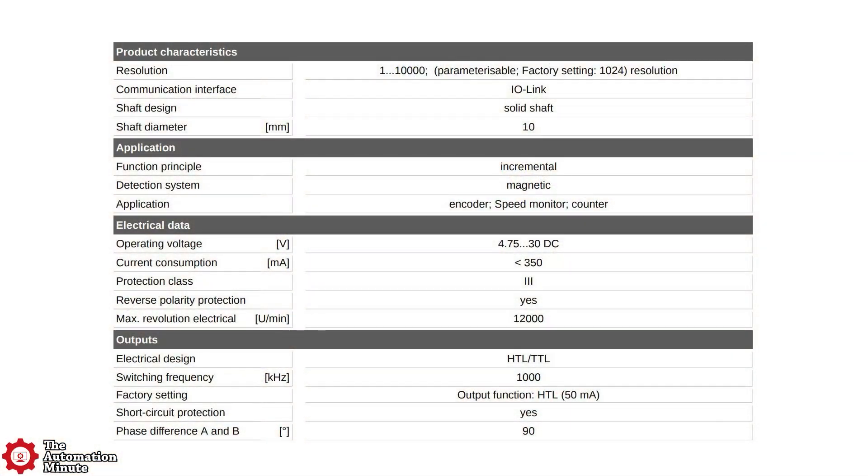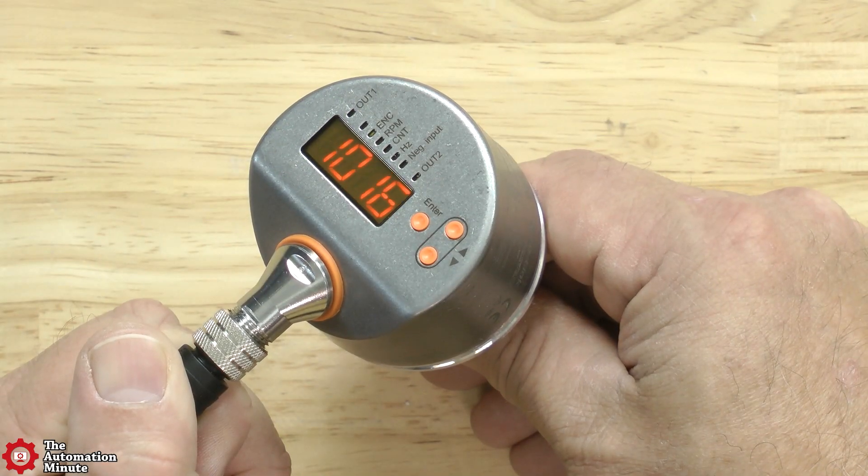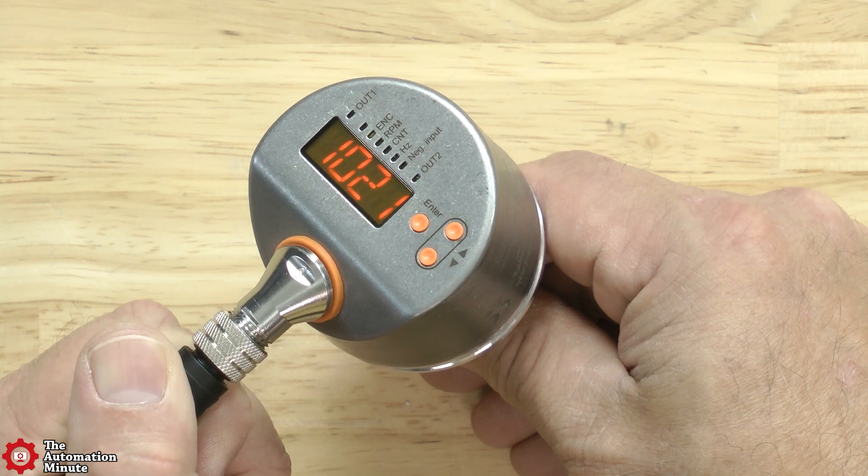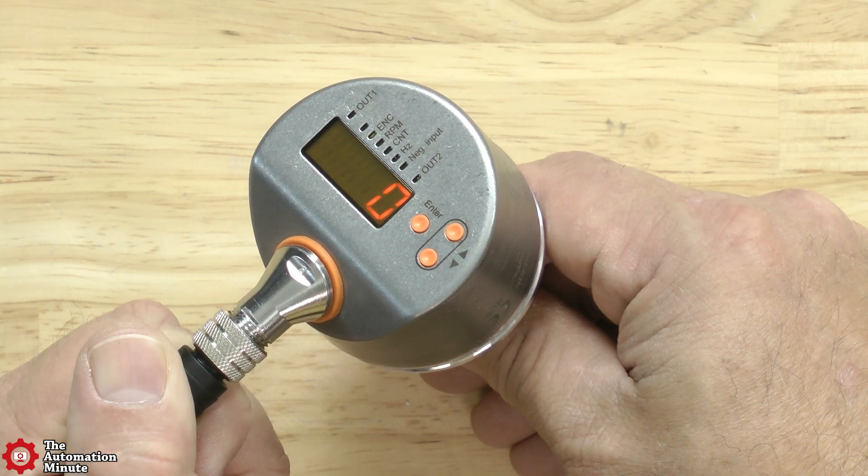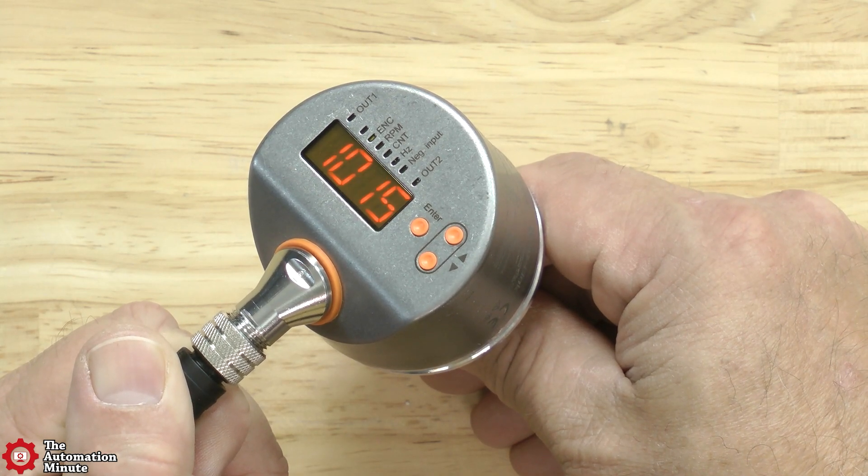It has a solid shaft with a 10 millimeter diameter and can be configured for a resolution anywhere between 1 and 10,000 pulses per revolution, but comes from the factory set at 1,024 pulses per revolution.